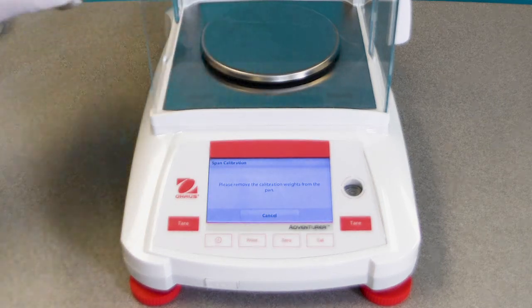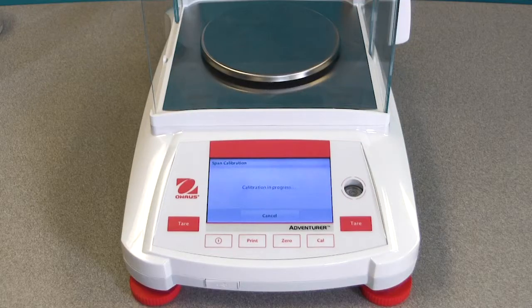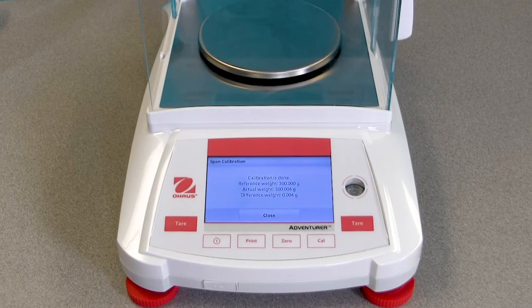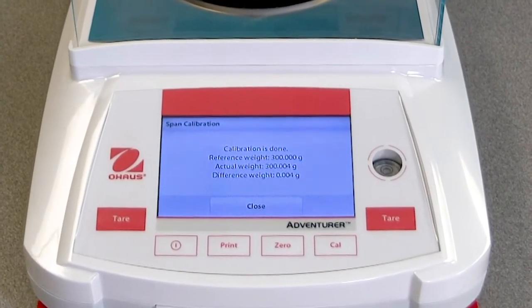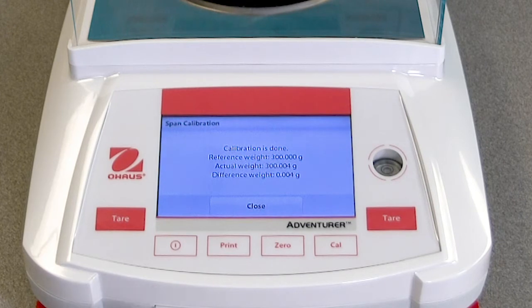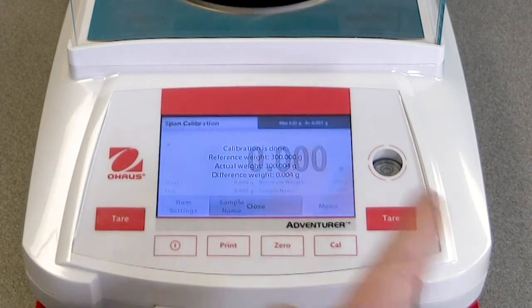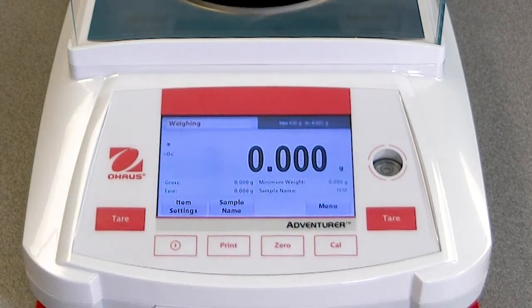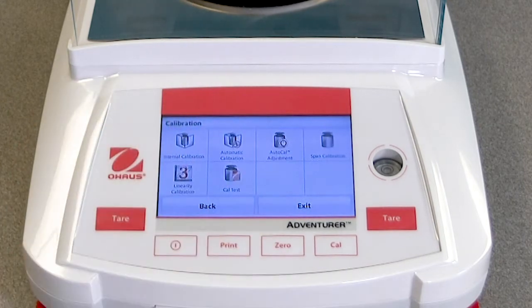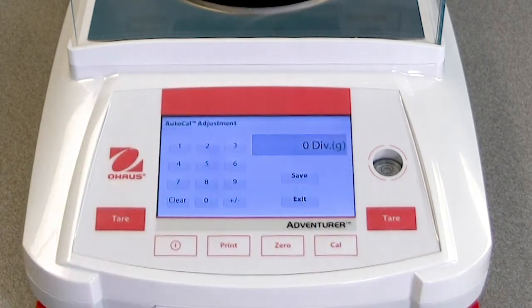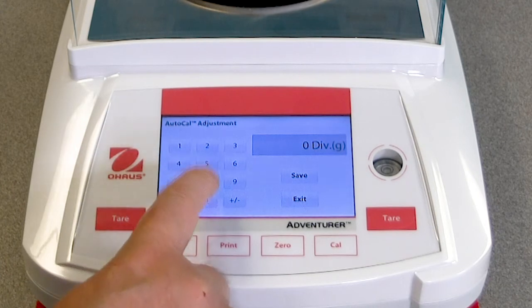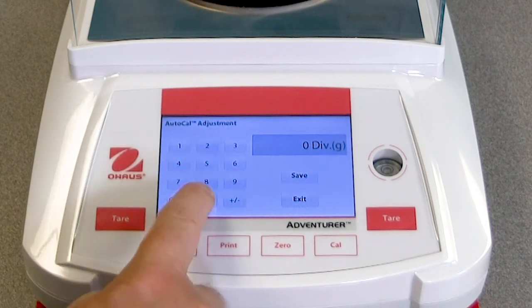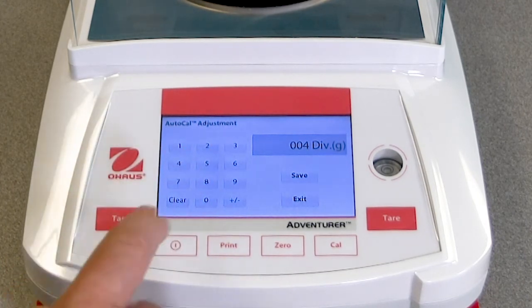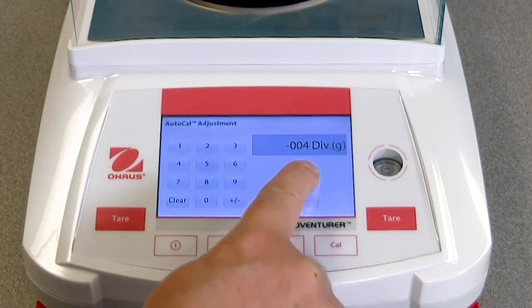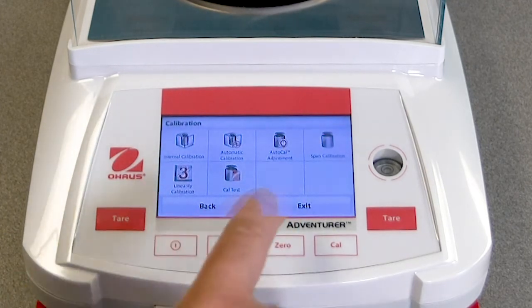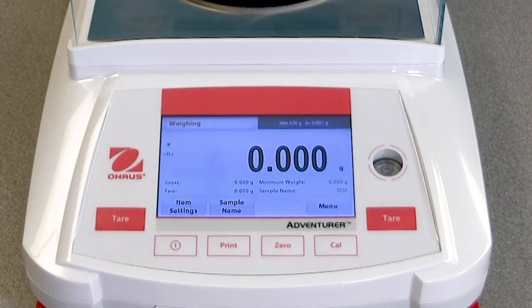If the difference is within plus or minus one division, calibration adjustment is not required. If the difference exceeds plus or minus one division, calibration adjustment is recommended. To perform a calibration adjustment, touch AutoCal adjustment from the calibration menu. Enter the value, positive or negative divisions, to match the difference noted earlier in the procedure. Recalibrate using internal calibration.